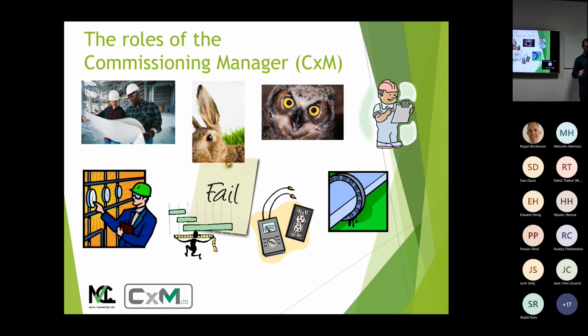Once the systems are installed, there's some pre-commissioning tests such as pipework pressure tests, ductwork pressure tests, cable testing, and point-to-point testing. That's one of the first things that doesn't get done particularly well on the control side, because they'll rely on the software to do the point-to-point testing of the cables. It's always good to get the installer - often not the control company, it'll be the M&E contractor, wherever they fit in - to check their cables are going to the right place, correctly identified and correctly terminated. Because all it takes is two cables to be swapped and your system doesn't work.